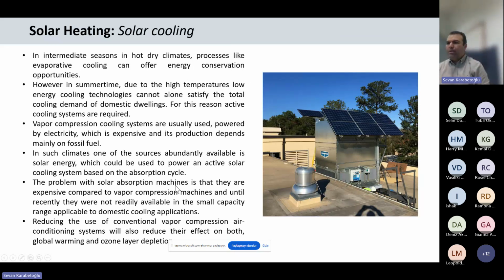And also we have solar cooling, of course, for the intermediate seasons in hot, dry climates. Processes like evaporative cooling can offer energy conservation opportunities. However, in summertime, at higher ambient temperatures, low energy cooling technologies cannot alone satisfy the total cooling loads. Therefore, vapor compression cooling systems are usually used in those cases, powered by electricity, and they are also expensive and large systems. So in those high ambient temperature conditions, we can implement solar energy based cooling systems.